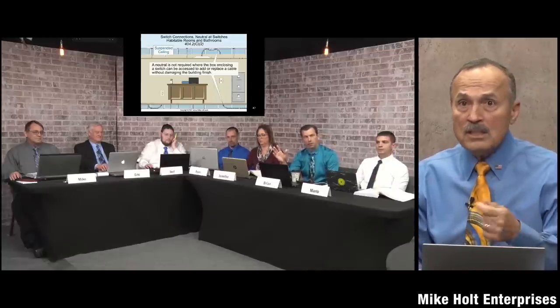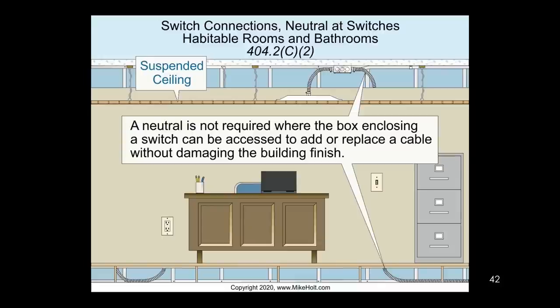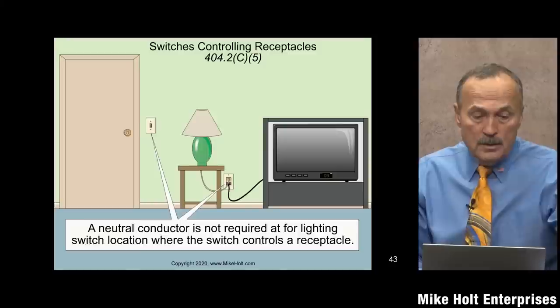Most electricians would say just put in neutrals where required. The code says if you can get a neutral there later — either through a raceway system or accessible space — you don't have to put one in now. When you're wiring thousands of locations in a large building, not pulling thousands of extra feet of wire just for neutrals makes practical sense.